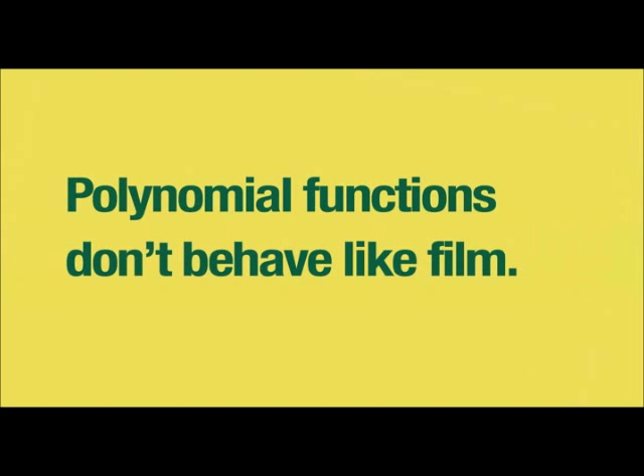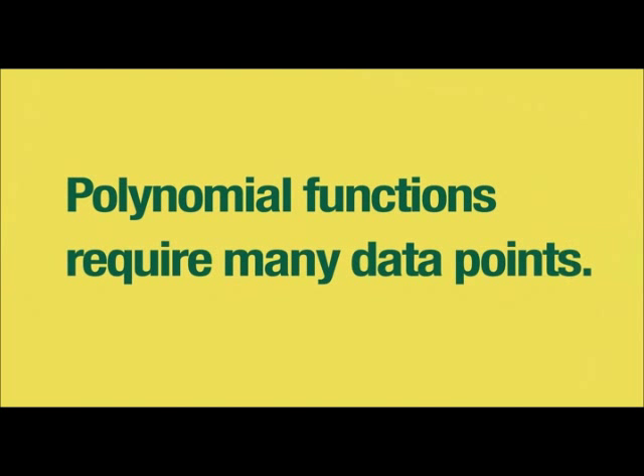And why only four? Well, FilmQA Pro 3.0 uses a special mathematical function. The polynomials usually used to fit calibration data have severe drawbacks, and they often oscillate between the data points. And outside the range, they behave very differently from film. So to get a smooth fit using polynomials, some people advise 12 or more data points.